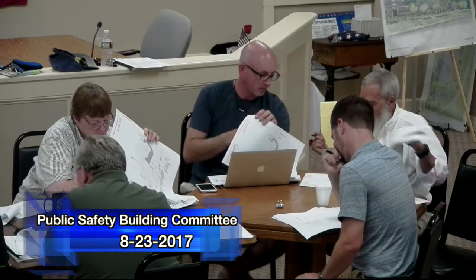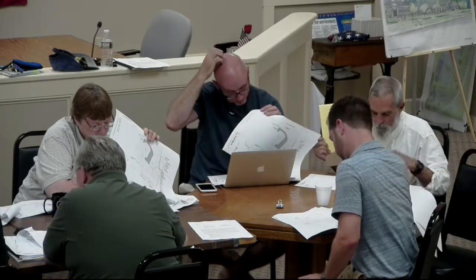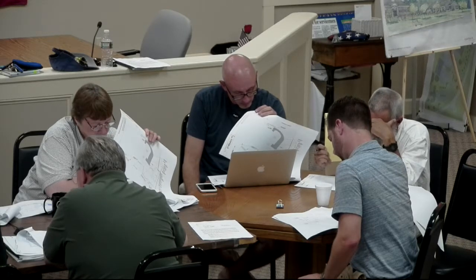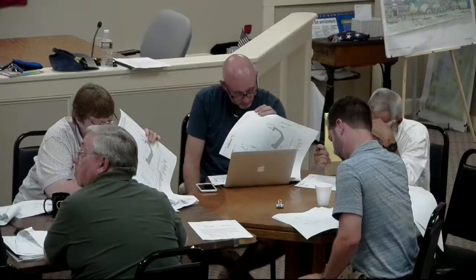The advice is that those should be separated by a minimum of 5 to 7 feet, and should be approximately at least 7 to 10 feet away from the building. There should also be some clearance for any vehicle that might need to get back there for some reason, and that's how they arrive at the recommendation of 15 to 20 feet. Not to mention, depending on the size of the trees and branch spread, that's also a good reason to make sure there's enough clearance behind the building, to keep that tree line away from it. Currently, what we're showing is a transformer, as you can see in the corner, marked by a T, it's a square.